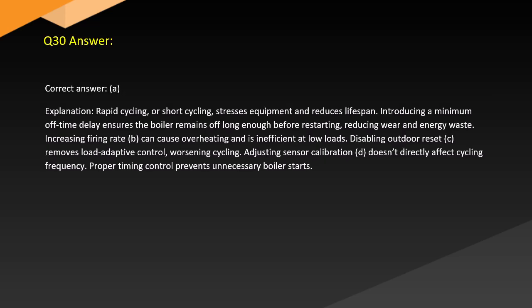Answer. Correct answer: A. Explanation: Rapid cycling, or short cycling, stresses equipment and reduces lifespan. Introducing a minimum off-time delay ensures the boiler remains off long enough before restarting, reducing wear and energy waste. Increasing firing rate, B, can cause overheating and is inefficient at low loads. Disabling outdoor reset, C, removes load adaptive control, worsening cycling. Adjusting sensor calibration, D, doesn't directly affect cycling frequency. Proper timing control prevents unnecessary boiler starts.